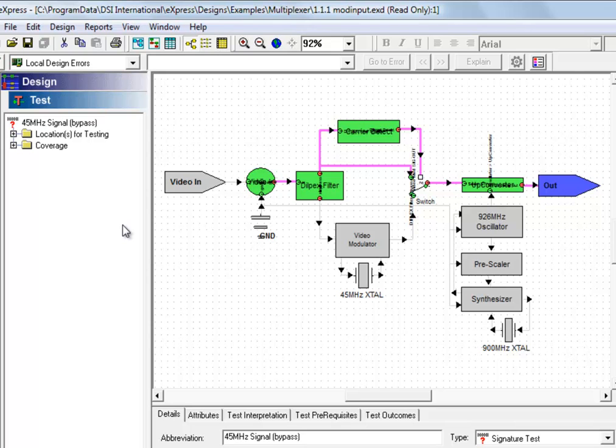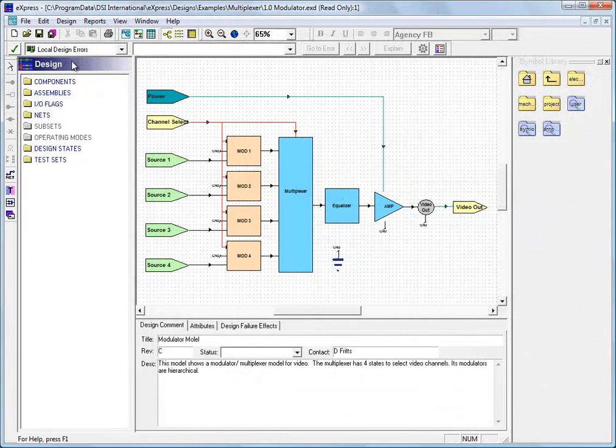These green items are part of the coverage, and when changes are made at this level and this model is saved, those changes at this level are inherited back up through the design up to the top level. It's this type of information that is used in the diagnostic studies to generate the hierarchical systems fault detection and fault isolation percentages, as well as a host of other reports that are useful for optimizing low-level and system-level diagnostics and BIT design. This approach also elegantly enables the swift embracing of design iterations or changes that may occur during design development or at any time during the sustainment of the design.